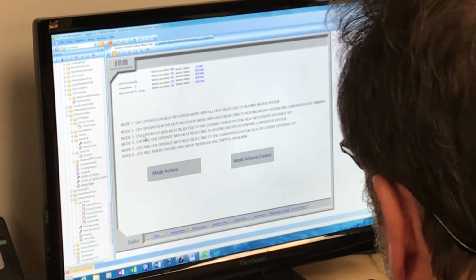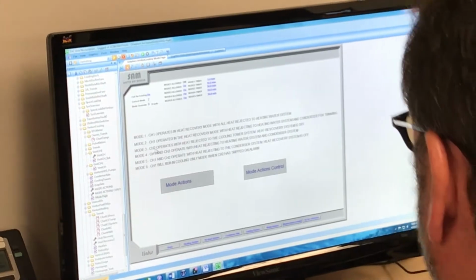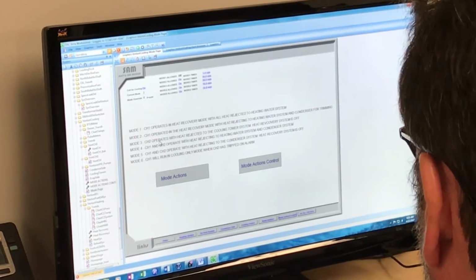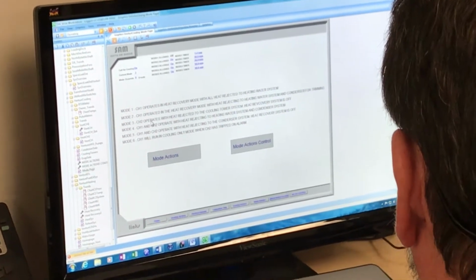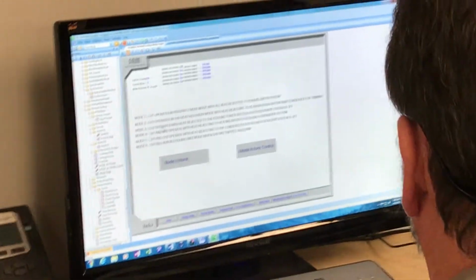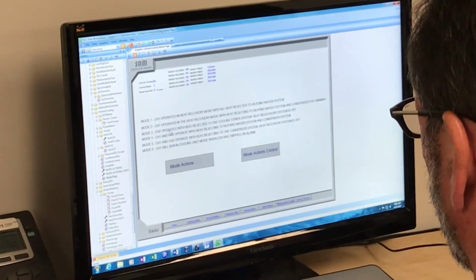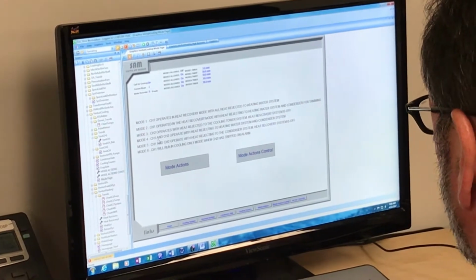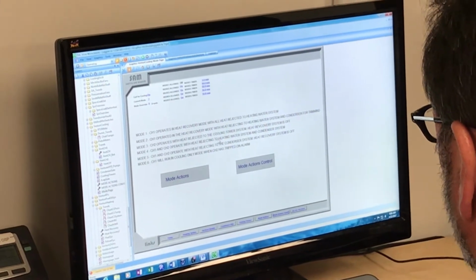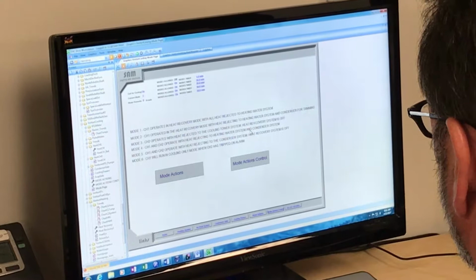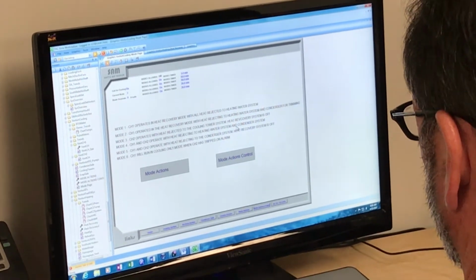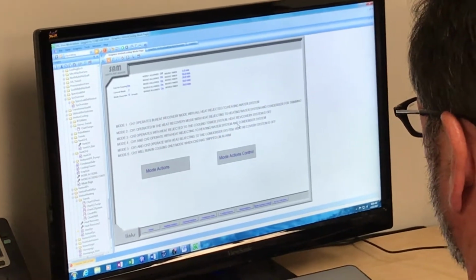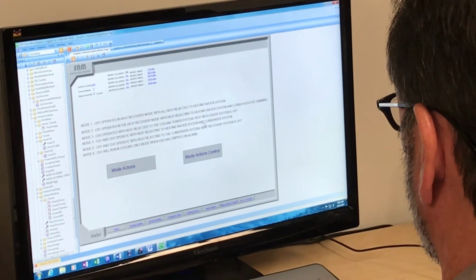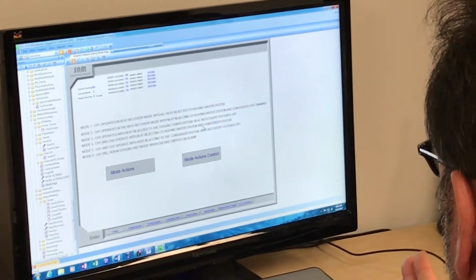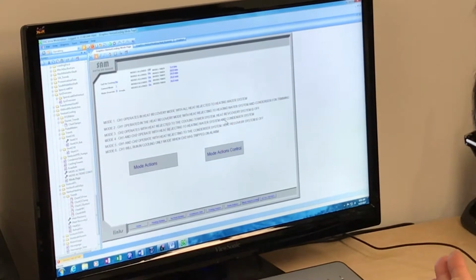So mode 3 is chiller cooling only, and chiller 2 is operating. So you're cooling only, heat rejected into the cooling tower. Right. Heat recovery system is off. Okay. Mode 4, CH1 and CH2 operate with heat rejected to the heating water system and condenser system. What's that mean, Sam? Mode 4 is just both chiller 1 and chiller 2 running together. That's just cooling only, right?